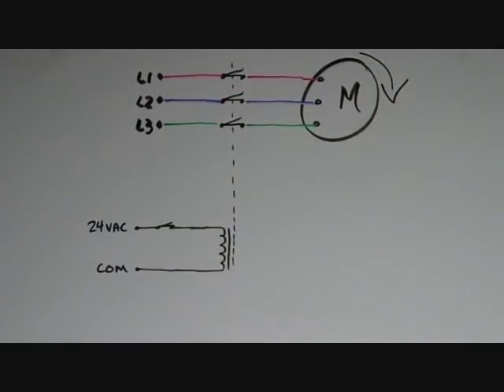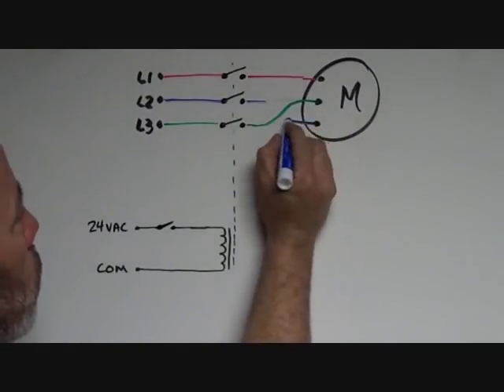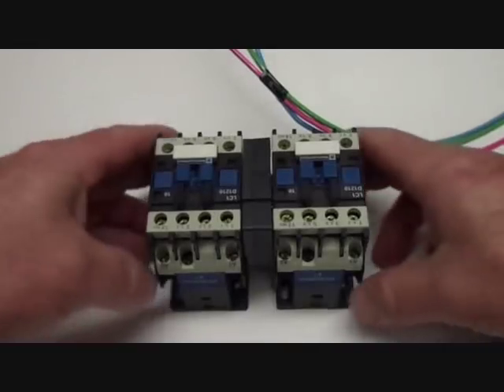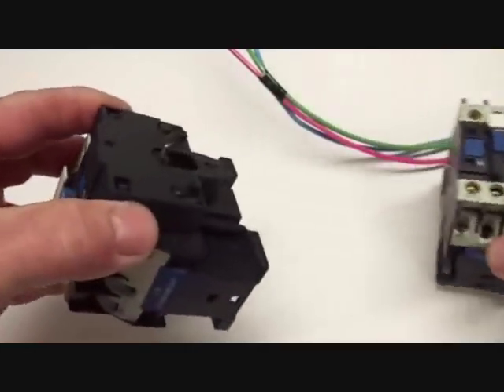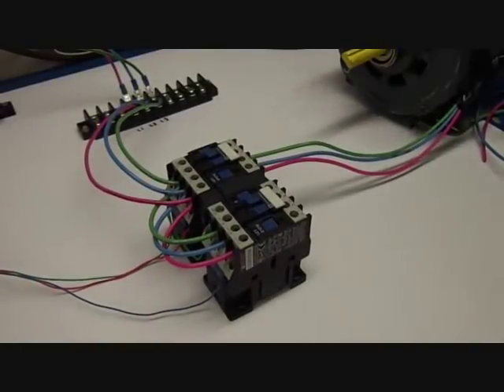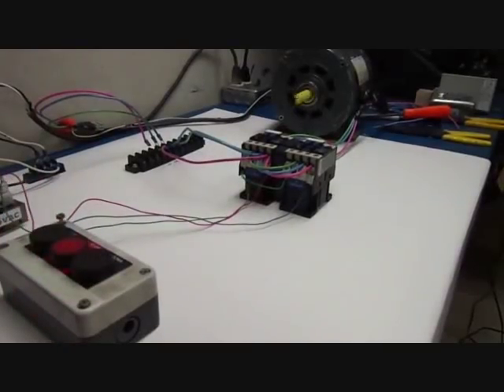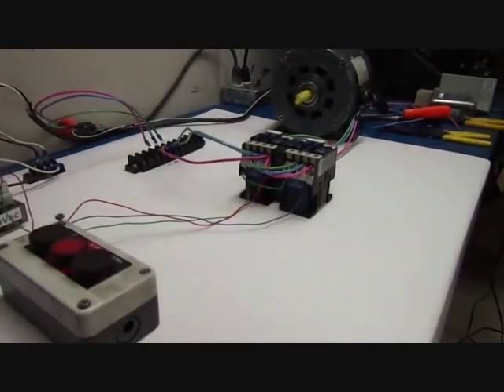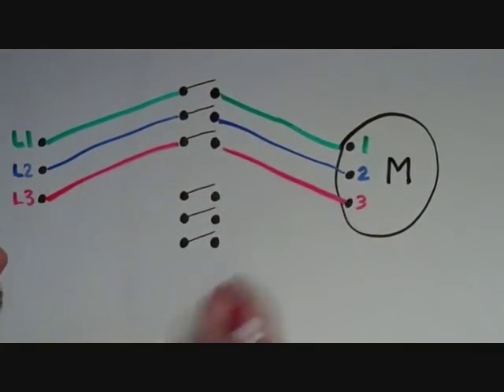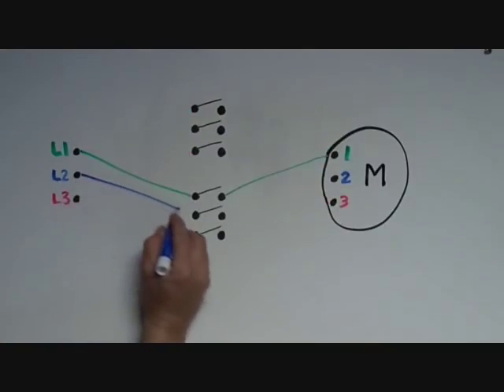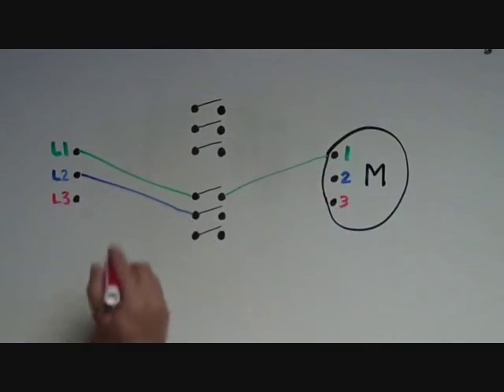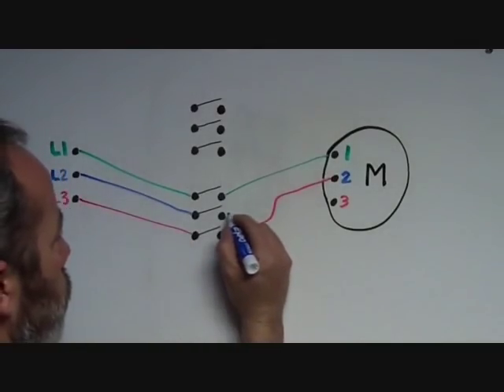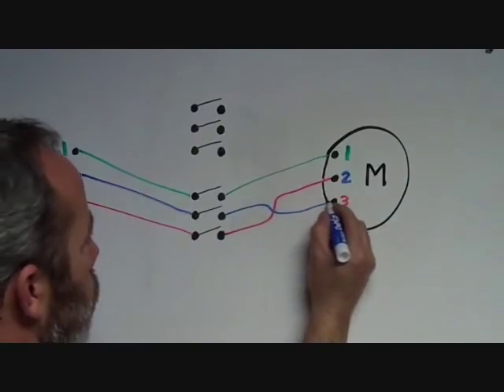If I were to swap any two of the three phases, the motor would run in the other direction. That's where the other contactor comes into play. The first one will be our clockwise contactor, and the second one will be our counterclockwise contactor. So here's our two contactors, each with their own button to send 24 volts to their individual coils. The original clockwise contactor is hooked up just like we had it. The counterclockwise contactor is going to get 460 volts from the same source as the other one, and the load side is going to get connected to the same motor, but with phases 2 and 3 swapped.